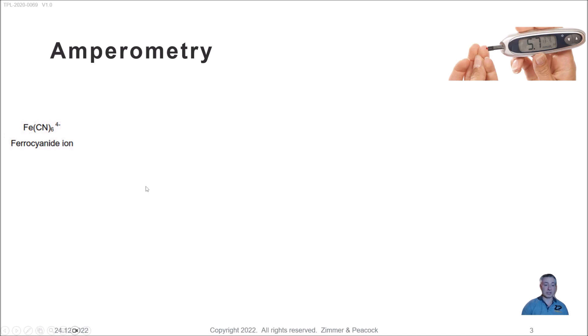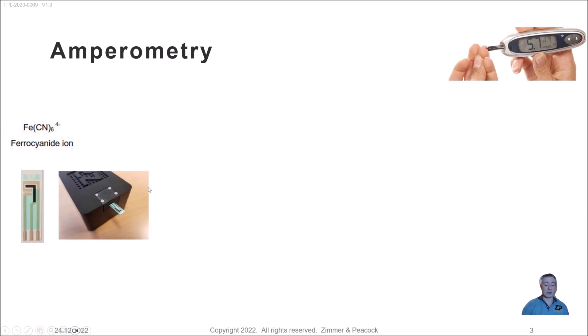In amperometry — an important technique with at least a hundred different manufacturers of glucose strips, most of which are electrochemical — they all have a charging current phenomenon. I'll give an explanation of charging current using ferrocyanide as an example. We have a solution of ferrocyanide that we might put onto an electrode system, dropping it on, and then the potentiostat will run an amperometric experiment.